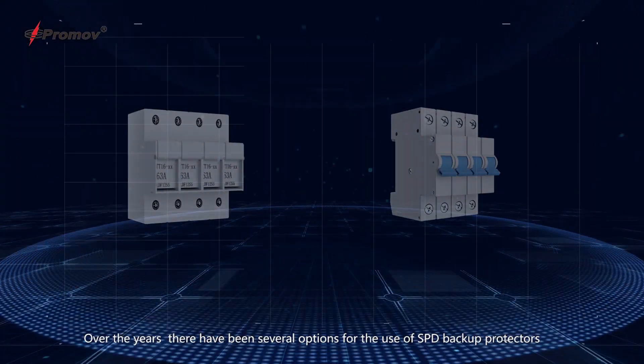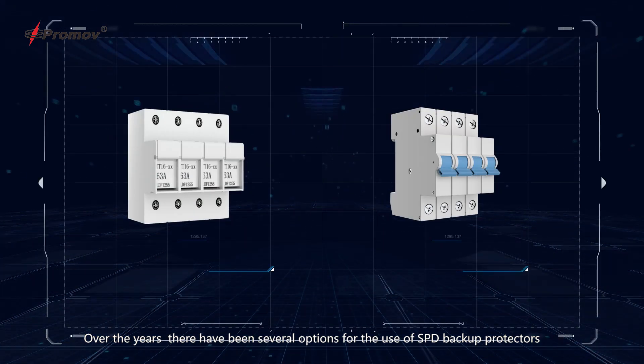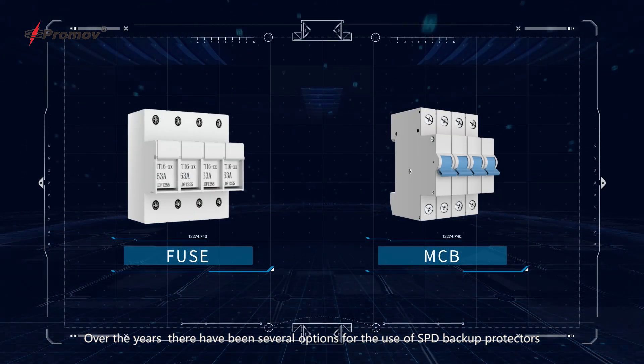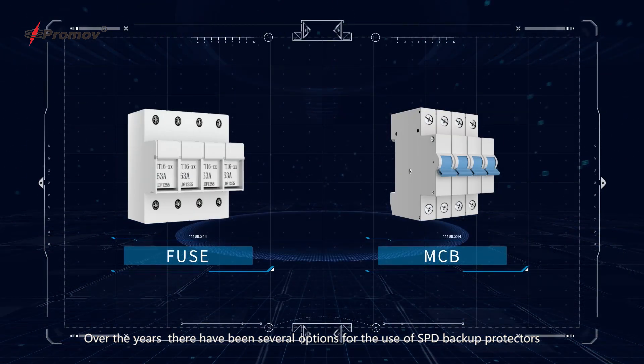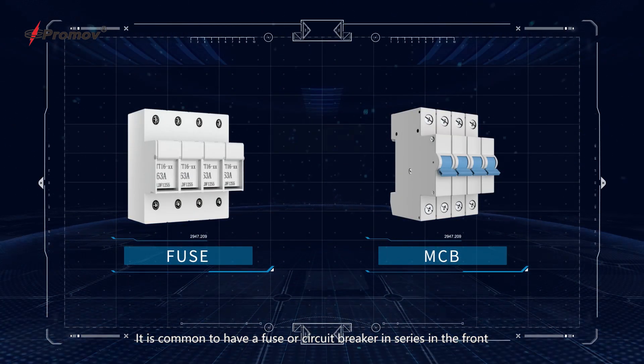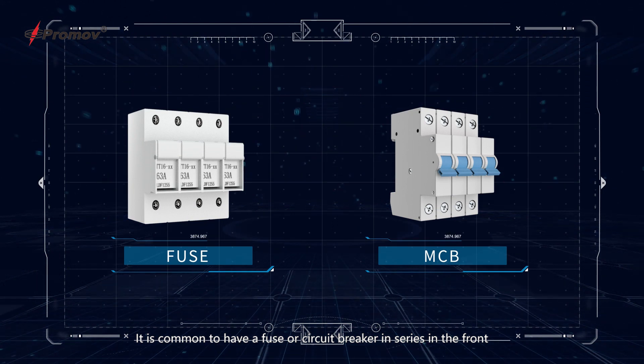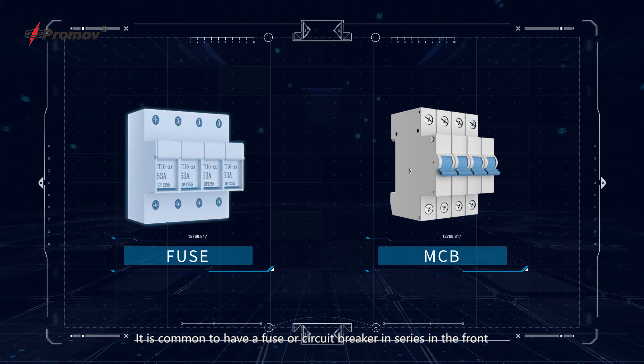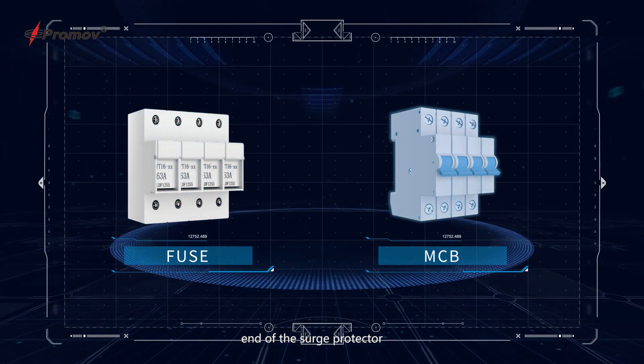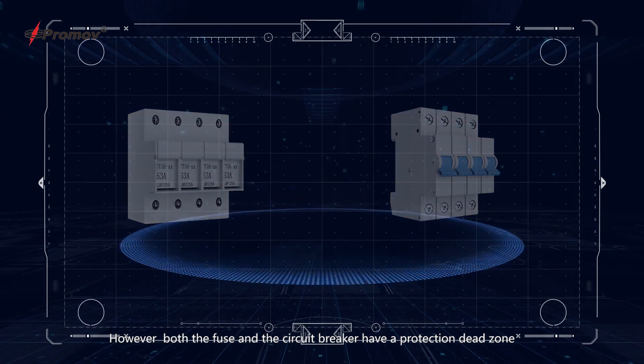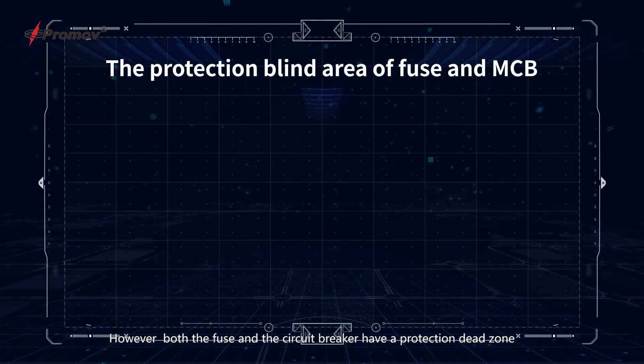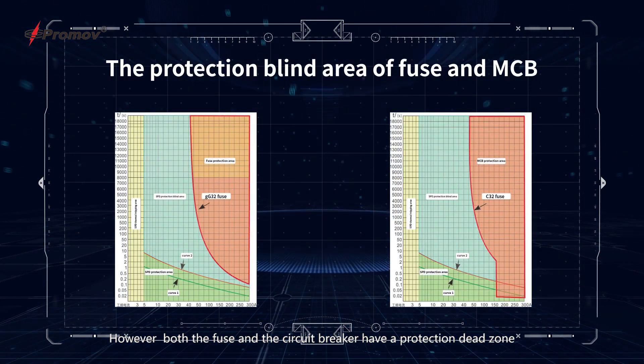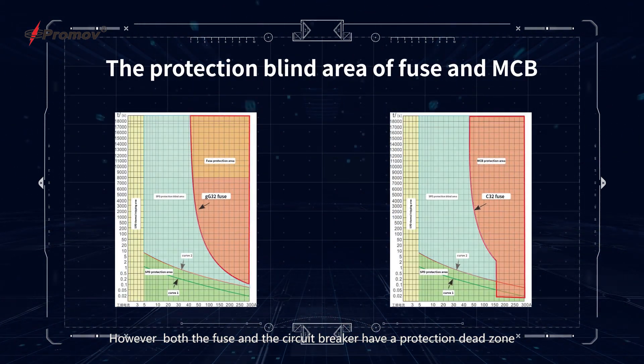Over the years, there have been several options for the use of SPD backup protectors. It is common to have a fuse or circuit breaker connected in series at the front end of the surge protector. However, both the fuse and circuit breaker have protection defects.